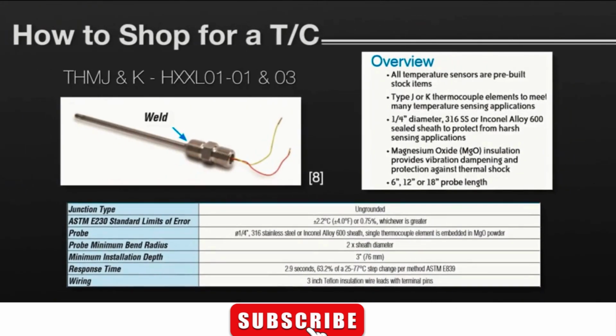Let's find the thermocouple probe online. This straight probe from Automation Direct has a pipe plug on it for screwing it directly into the wall of a furnace or an oven. You can buy it as a type J or K calibration with a 1/4 inch, that's 6.3 millimeter outer metal sheath made of either 316 stainless steel or Inconel. Both of those sheath materials do stand up very well to the corrosive environment of a furnace.